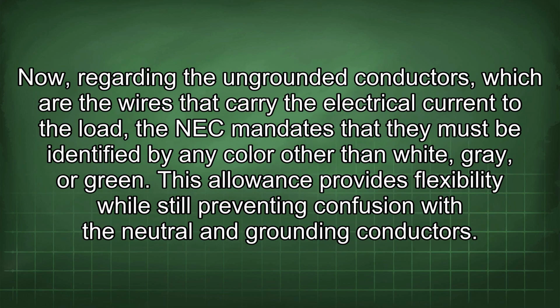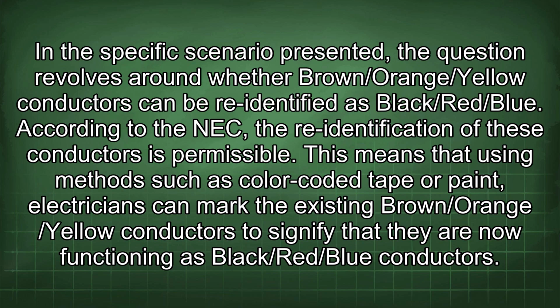Now, regarding the ungrounded conductors, which are the wires that carry the electrical current to the load, the NEC mandates that they must be identified by any color other than white, gray, or green. This allowance provides flexibility while still preventing confusion with the neutral and grounding conductors. In the specific scenario presented, the question revolves around whether brown/orange/yellow conductors can be re-identified as black/red/blue. According to the NEC, the re-identification of these conductors is permissible.